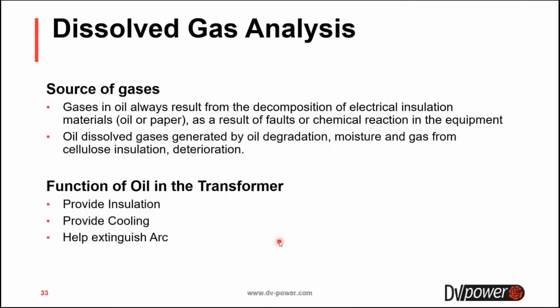Source of gas. Gas in oil always results from the decomposition of electrical insulation materials, oil or paper, as a result of faults or chemical reactions in the equipment.